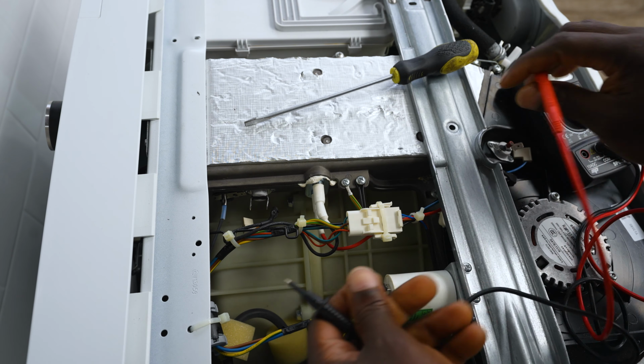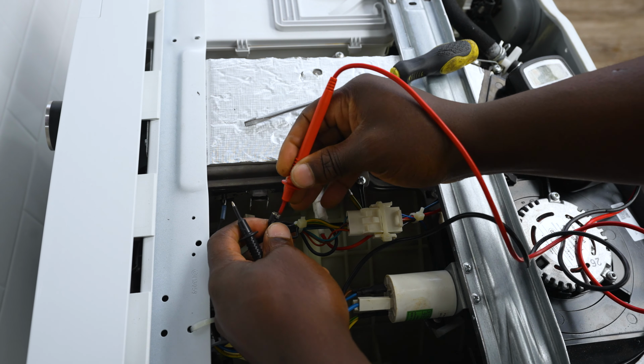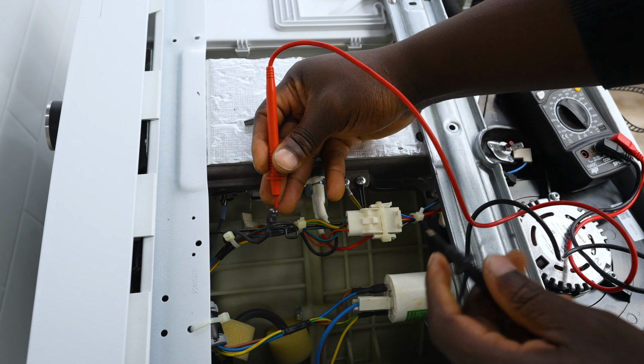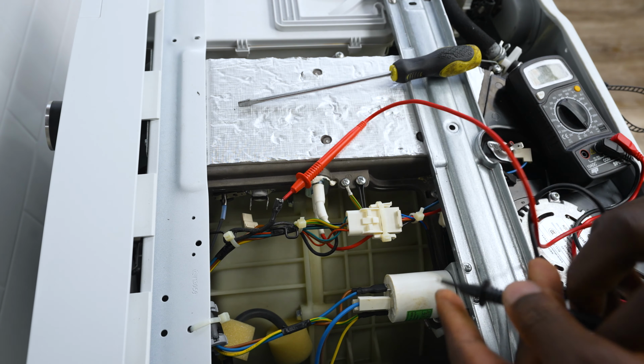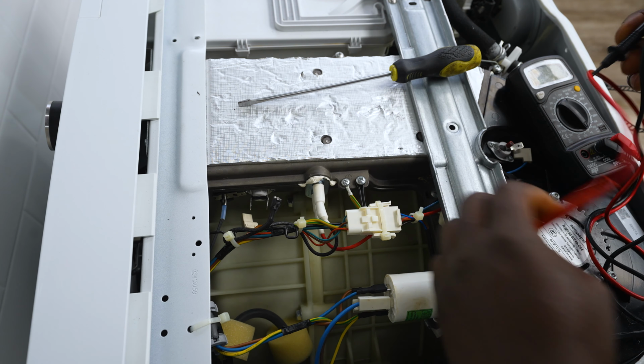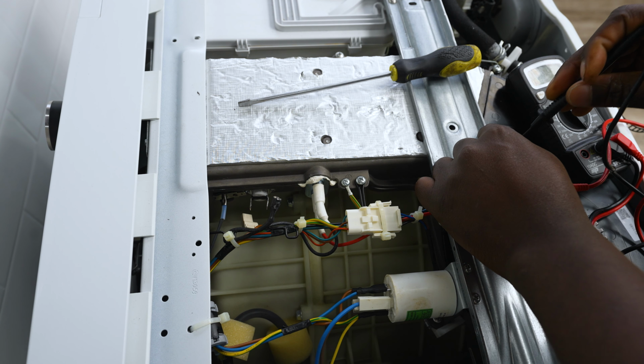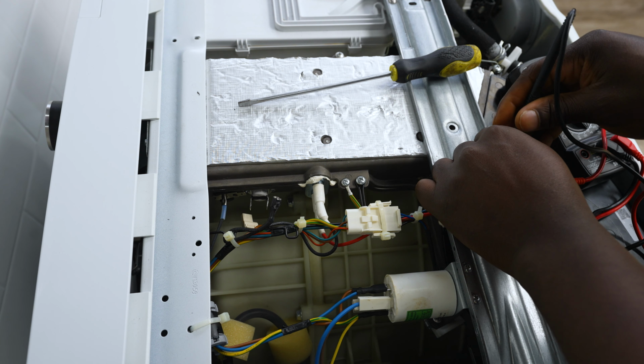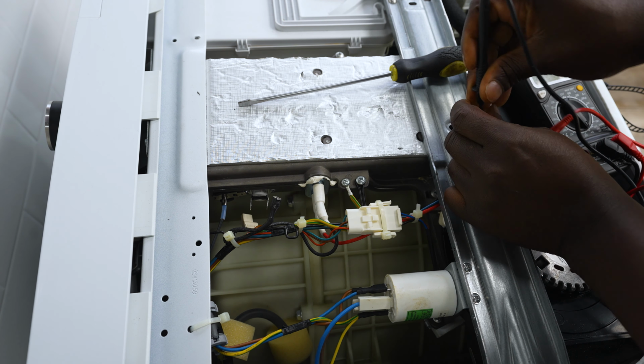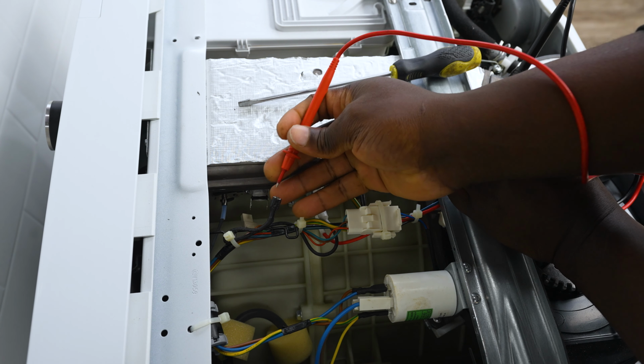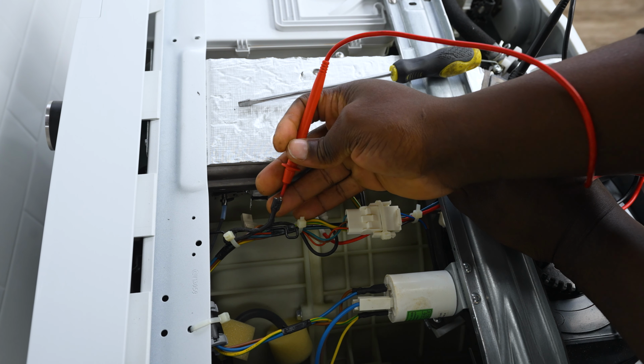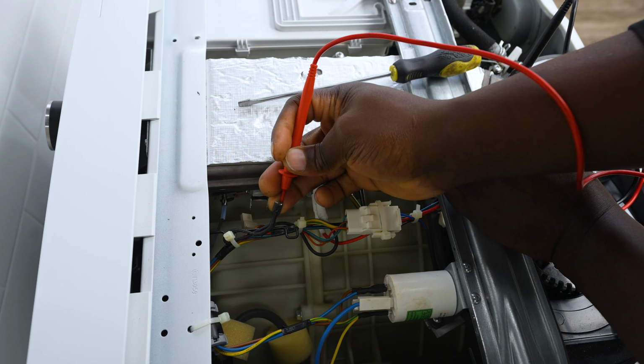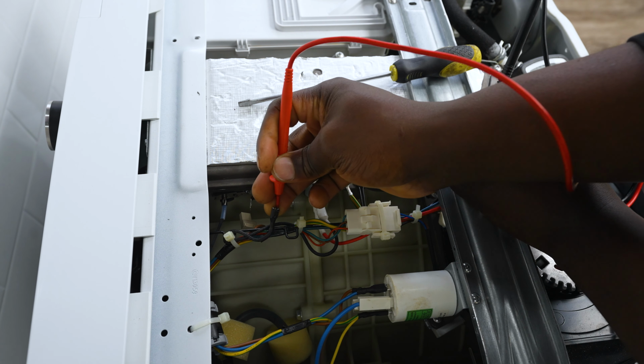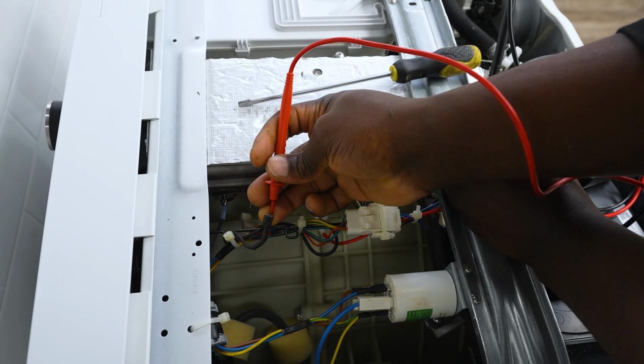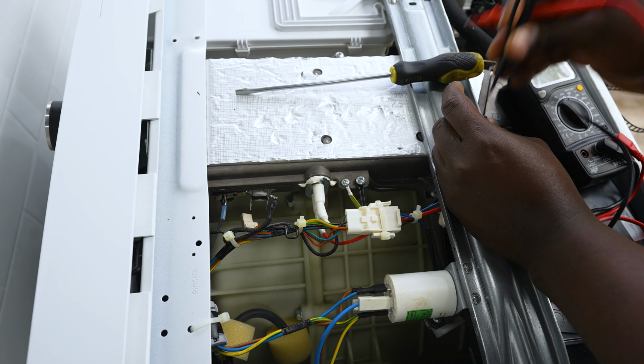We'll leave it on continuity, and probe one end into the black wire coming out of the heater, which is here, and the other one goes where we had the other resettable safety thermostat. I've got that in, and I'll put the other one on the other one. And I've got nothing. So once you do that, that means there's nothing — it's not working. That heater is not working.